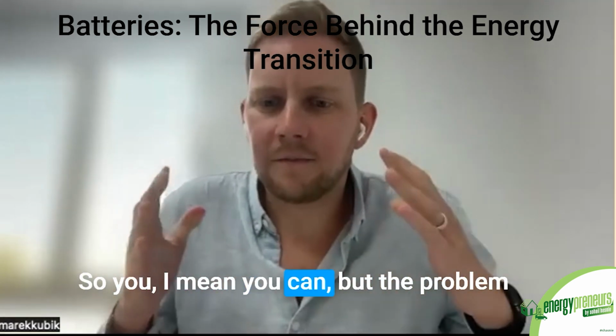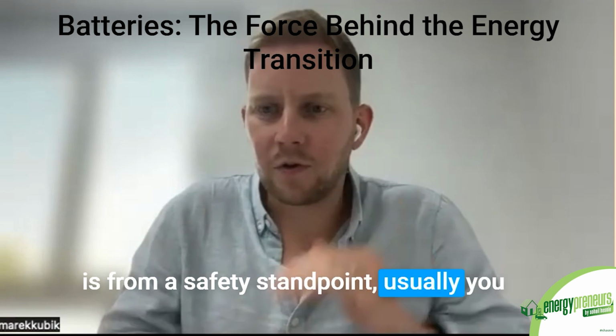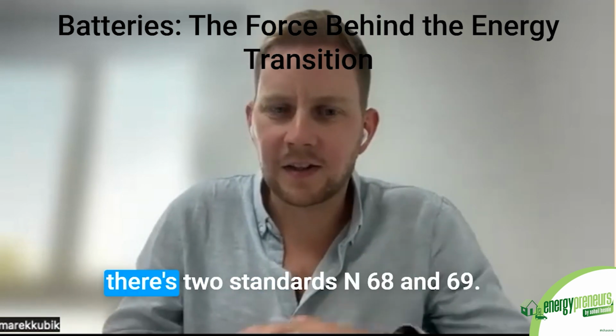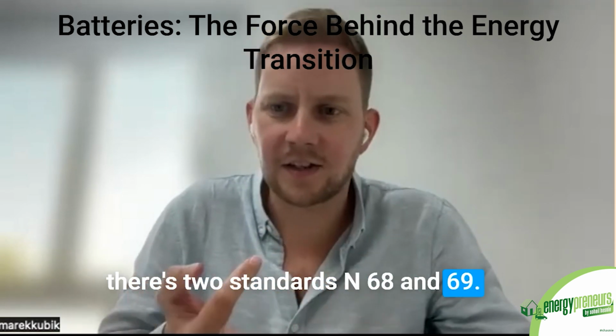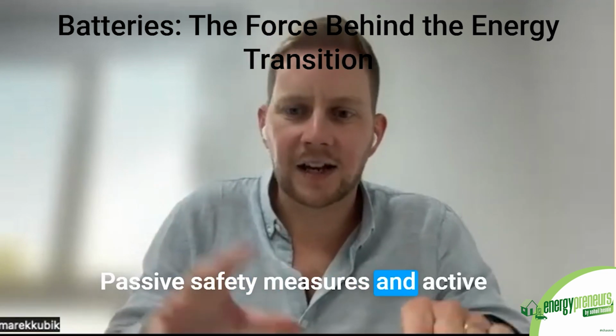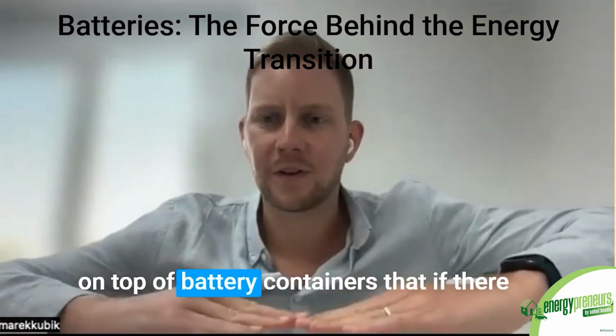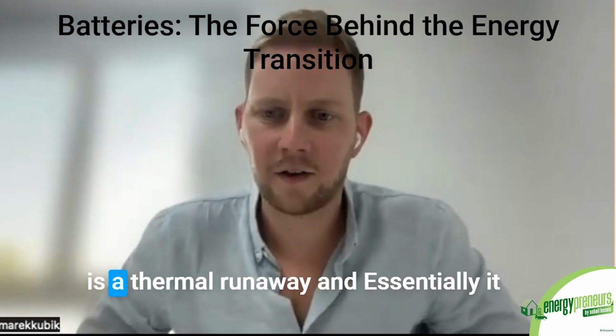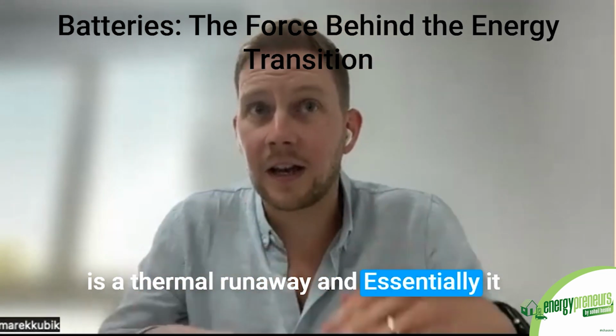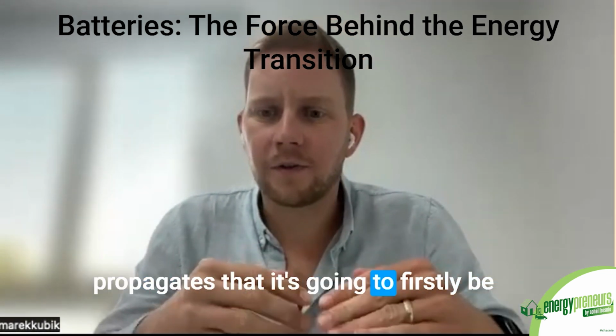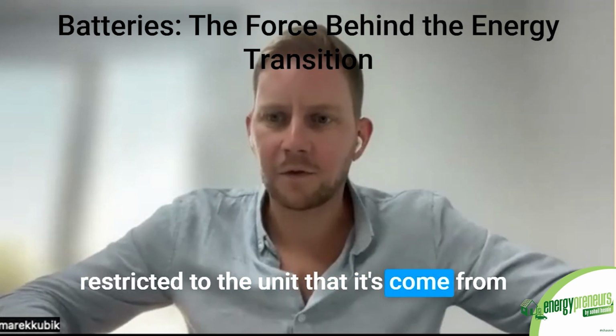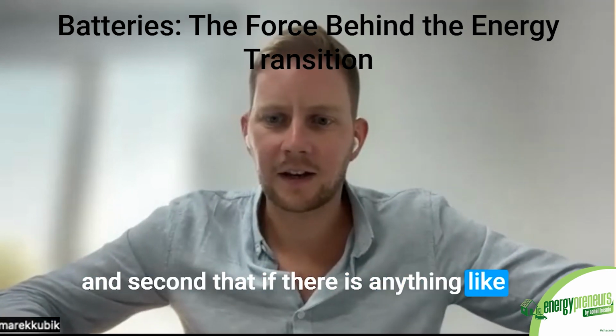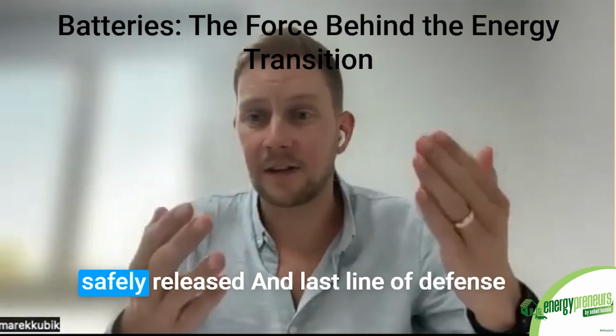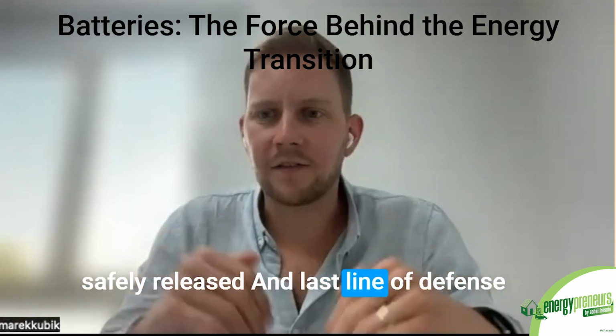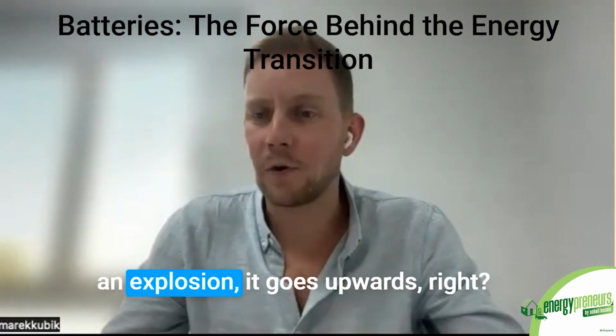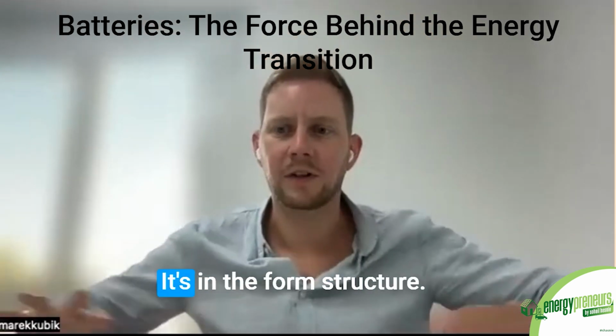You can stack, but the problem is, from a safety standpoint, usually you have what's called deflagration venting. There are two standards, NFPA 68 and 69 - basically passive safety measures and active safety measures, usually on top of battery containers. If there's a thermal runaway that propagates, it's going to firstly be restricted to the unit it's come from. Second, if there's any explosive gas buildup, the gas is safely released. And the last line of defense is, if something ignites an explosion, it goes upwards and doesn't go outwards in the form shroud.